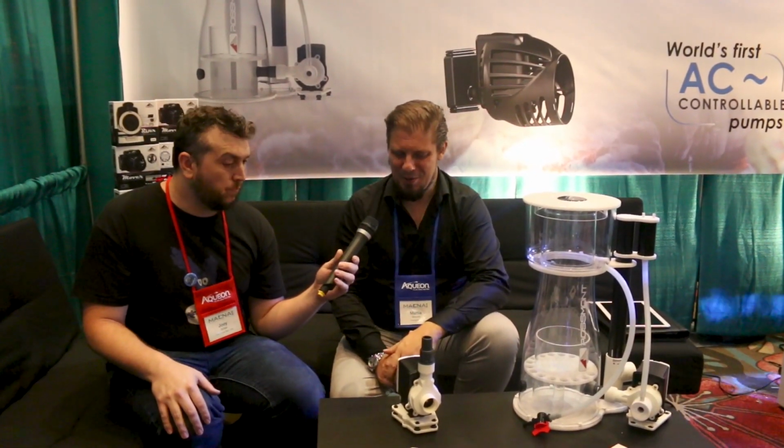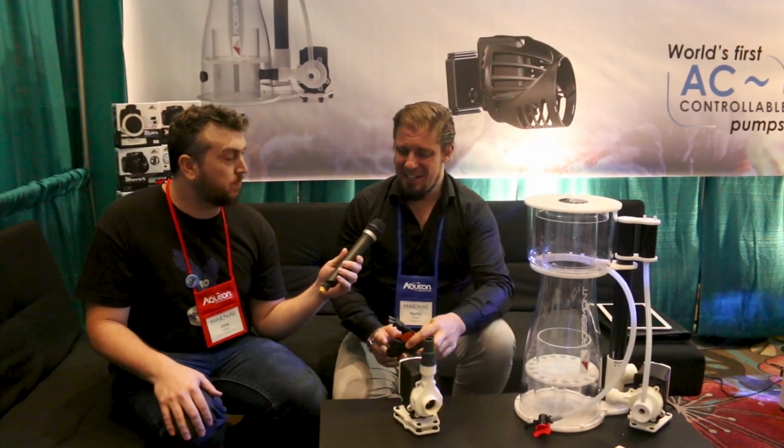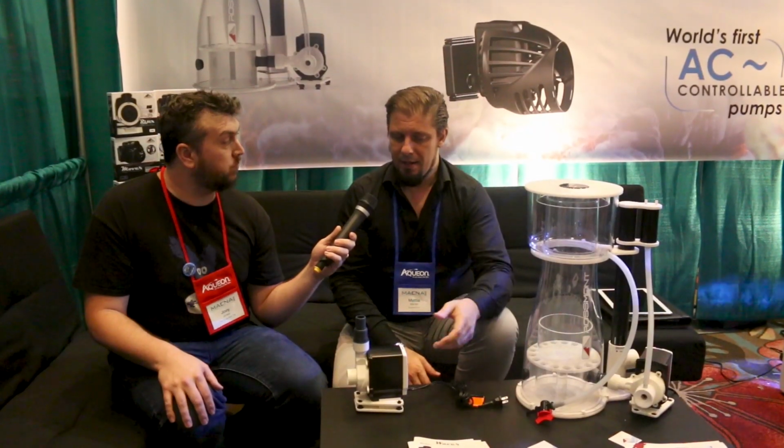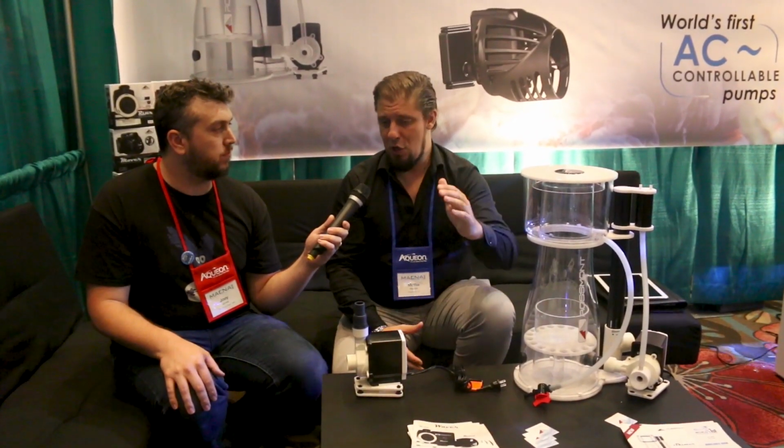Absolutely. You stole the word from me, because in technology, when you don't have something which can break, it doesn't break. So we decided to have pumps without any power supply, because normally with a DC pump, when the rotor gets dirty, if you don't continuously do maintenance, the pump starts to slow down in speed. Your flow decreases. With an AC pump, it has the frequency of your mains voltage determining the speed of rotation, and it's 60 hertz.